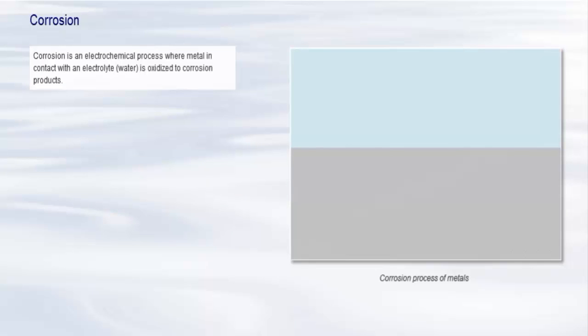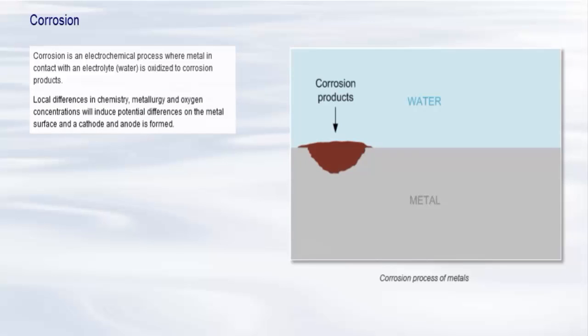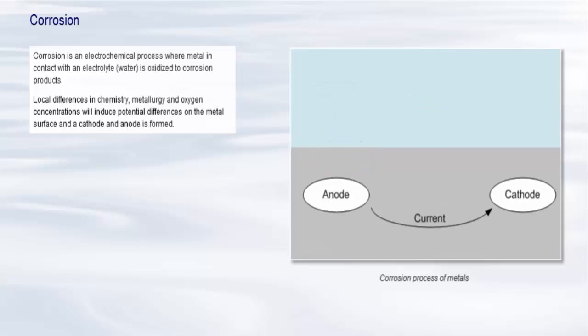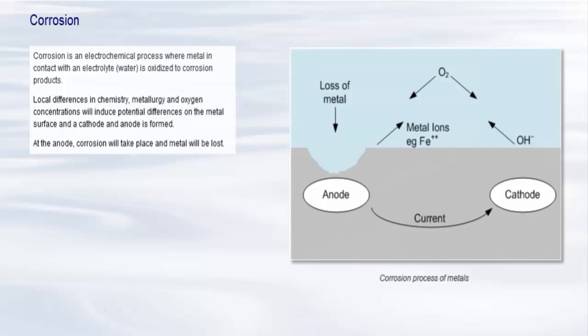Corrosion is an electrochemical process where metal in contact with an electrolyte, water, is oxidized to corrosion products. Local differences in chemistry, metallurgy and oxygen concentrations will induce potential differences on the metal surface, and a cathode and anode is formed. At the anode, corrosion will take place and metal will be lost. Characteristic deposits of iron oxide rust are also formed.